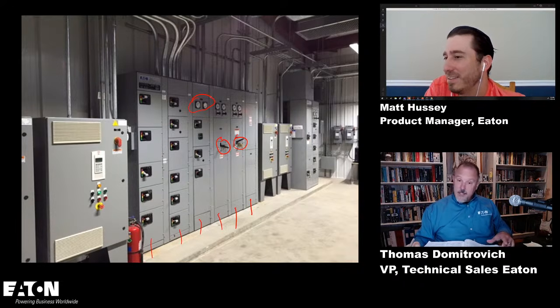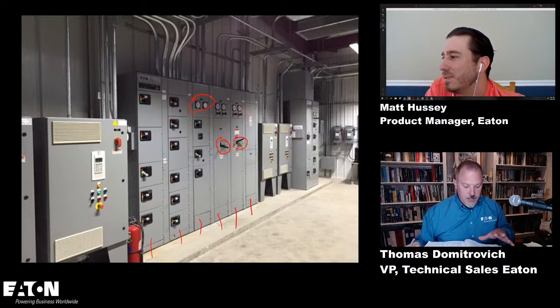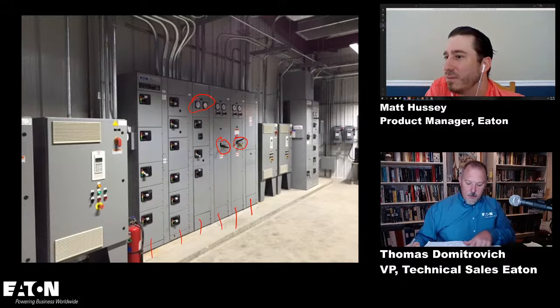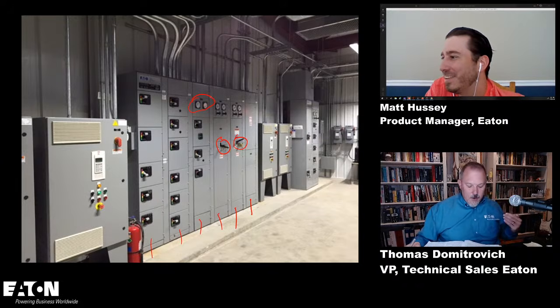110.26(A) is working space. So working space is important. And we know the 2020 code cycle did a lot of changes around working space, especially for large equipment. 110.26(A)(3) talks about height of working space. The workspace shall be clear and extend from the grade, floor, or platform to a height of 6.5 feet or the height of the equipment, whichever is greater. Other equipment or support structures such as concrete pads, I love it, associated with the electrical installation and located above or below the electrical equipment shall be permitted to extend not more than 6 inches beyond the front of the electrical equipment.